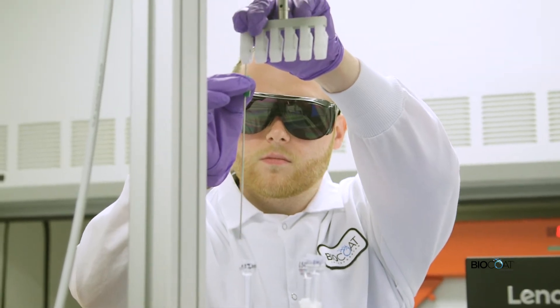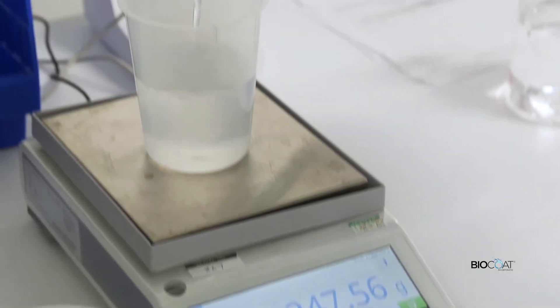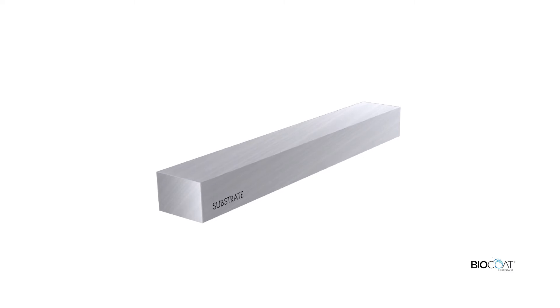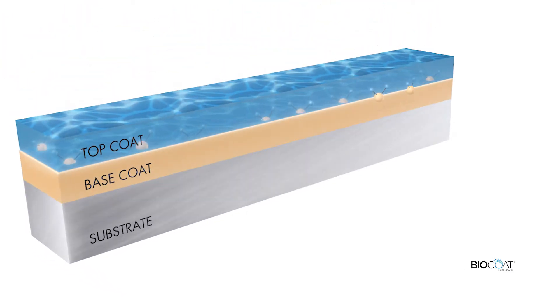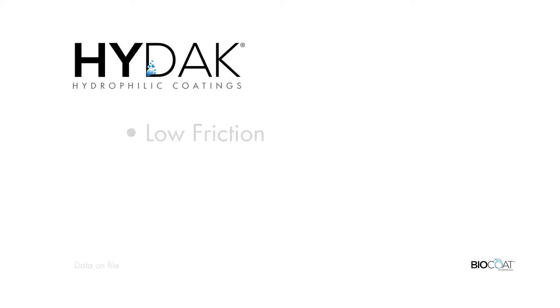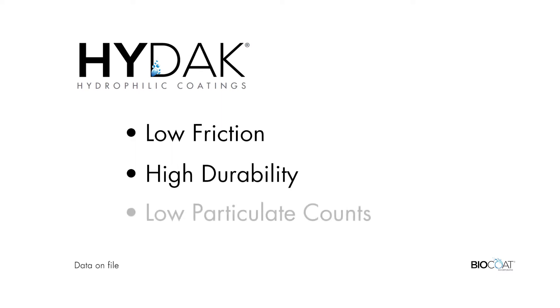Our HYDAK coating technology is a proprietary formula based on hyaluronic acid, a naturally occurring substance present in the body. HYDAK coatings use a bi-laminar, two-layer platform consisting of a base coat and a top coat that are covalently bonded together. This unique system allows for low friction, high durability, and low particulate counts.